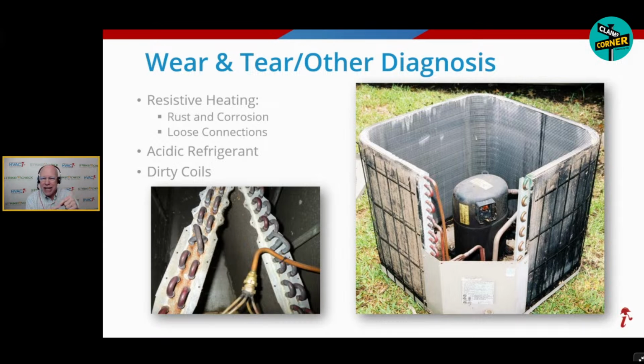Or the refrigerant's not changing state readily. It's supposed to be changing from a gas to a liquid as it's absorbing or giving up heat. And you get this thing called liquid slugging of your compressor, and you burn up your compressor because you have dirty coils.